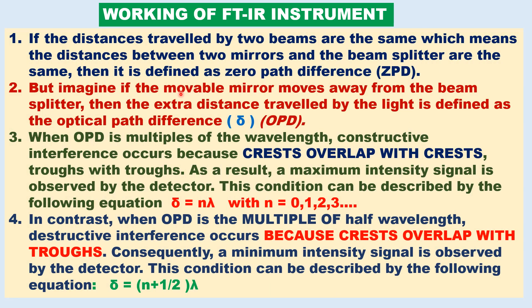Let us see the working of the FTIR instrument. If the distances traveled by the two beams are the same — that is, zero path difference — then constructive interference occurs. If the movable mirror moves away from the splitter, the extra distance traveled by the light is defined as the optical path difference, OPD, denoted by delta. When OPD is a multiple of nλ (n = 0, 1, 2, 3...), constructive interference occurs because crest overlaps with crest, and maximum signal intensity is observed by the detector.